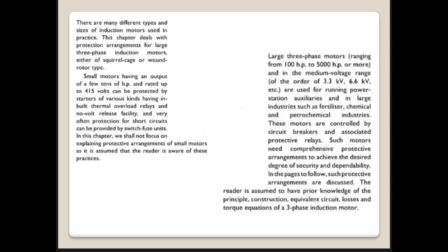Small motors of around 415 volt and a few tens of HP rating are not seen in this chapter because they are generally provided with the protection of fuse. Large three-phase motors ranging from 100 HP to 5000 HP are discussed here, and their voltage rating is medium voltage, ranging from 3.3 kilovolt to 6.6 kilovolt. Since they are widely used in industries like chemical, petrochemical, fertilizers, these motors have to be protected.